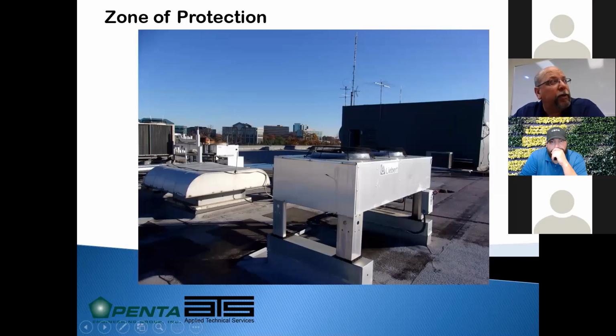We see a lot of instances where the original design of the lightning protection contained air terminals where they were necessary, but then a new tenant comes in, adds new mechanical equipment, and therefore needs modifications to the lightning protection. Then once you add lightning protection on this condensing unit, these would not be needed, because the ball could rest here and roll over onto here and not touch here. But you wouldn't necessarily have to demo those. They just wouldn't be necessary.